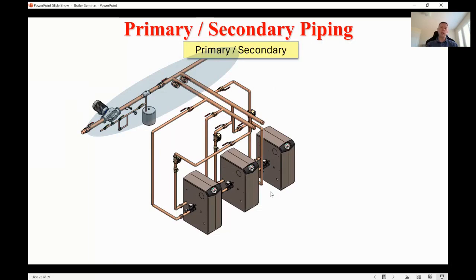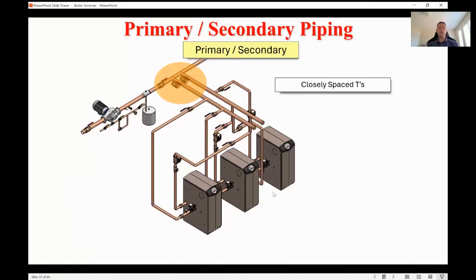And I think you guys all know that really the secret to making all this work is these two closely spaced T's. See those two, and it doesn't have to be, it can be a low loss header or buffer tank. But those two T's basically, as a general rule of thumb, they say maximum 12 inches apart or 4 pipe diameters. And the reason why that's like that is because the pressure drop between the inlet and the outlet there, because they're so close together, is negligible. And what that does is it accomplishes some hydraulic separation for you. So as that system pump turns on and off or ramps up and down, it won't affect the way the boiler pump operates on its curve. And as those boiler pumps turn on and off or potentially modulate, they won't affect the way the system pump operates on its curve. Each loop, the primary loop and the secondary loop, are hydraulically decoupled from each other. And that's the key, right?